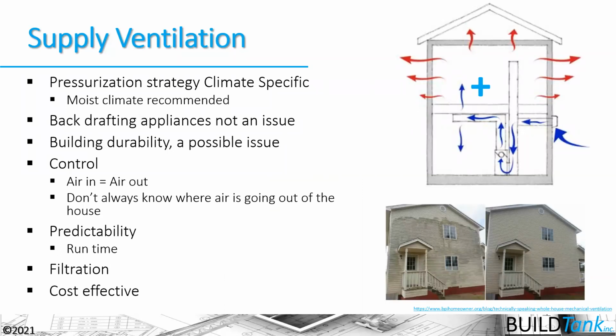pressurization strategy. In most moist climates, we recommend it because in general, there's less moisture inside the house than there is outside the house, in Louisiana or Houston, for example. So generally in those climate zones, a supply side ventilation strategy is liked better than an exhaust side ventilation strategy. But again, balanced ventilation would be the best, and we'll get to that here in a second.